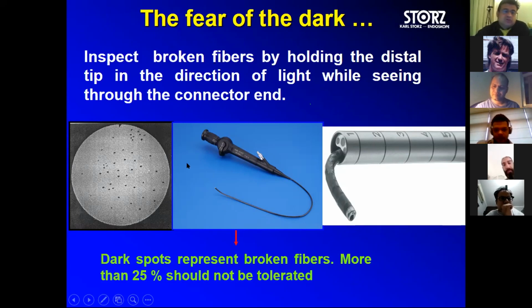it's safe. So the recommendation from Storz's factory is that if your area is covered by 25% black spots, then it is better to change it. And it is not possible then to do a reanastomosis of these fiber bundles which break. These are very small bundles, and we will have to change the assembly here. So I think it's good to have the new chip-on technology, because the visualization is not compromised. So this is another thing why it happens. And with continuous usage, yes, chances of bundles breaking will be there, but one should be careful by putting this. So this is another thing.